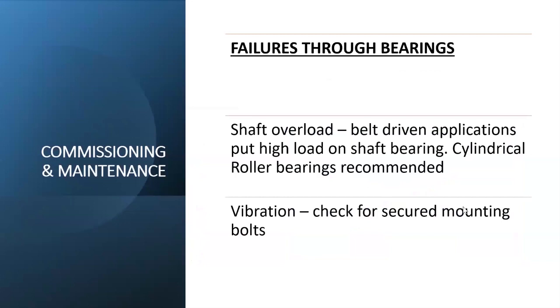Also, shaft overload, especially on motors which are belt driven. A lot of pressure is put on the motor at the drive end. Because of the pressure, the bearings do not operate freely and they are lost prematurely. So if you know your application will be predominantly belt-driven, you inform your manufacturer, and for the drive end bearing of the motors, a cylindrical roller bearing is recommended. If you use it for that application, you extend the life of the motor and the motor is okay.